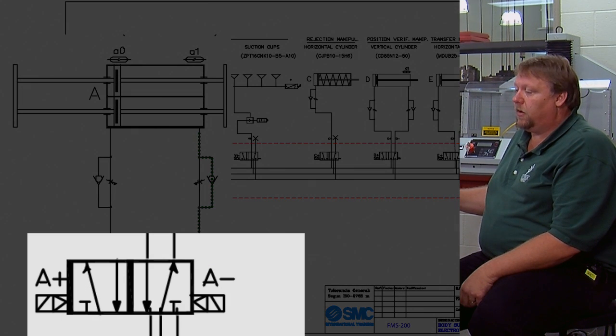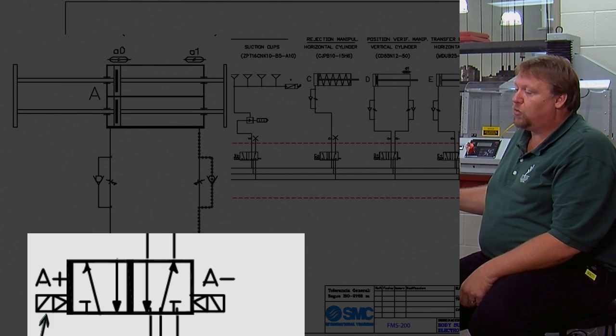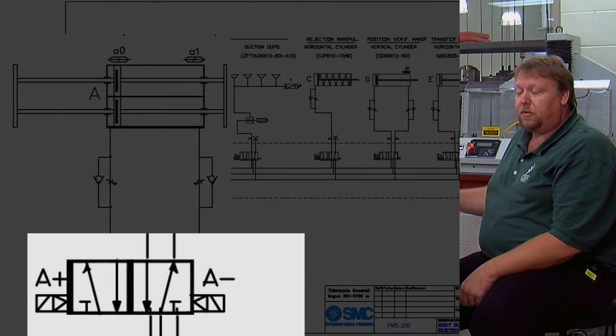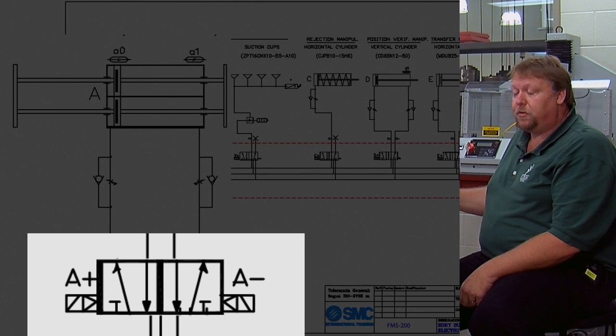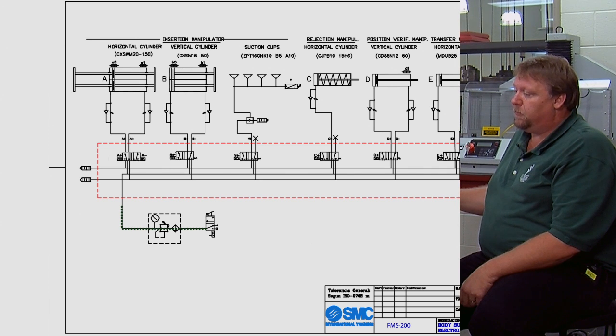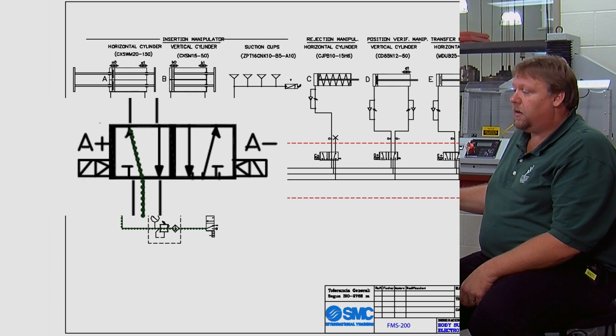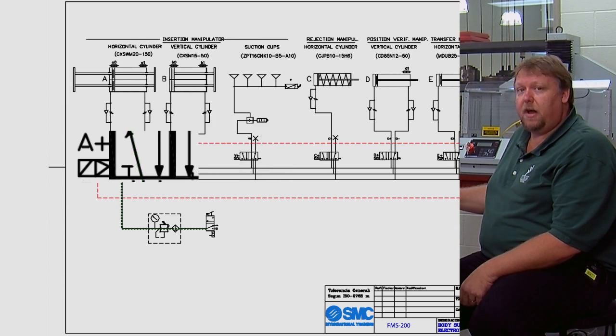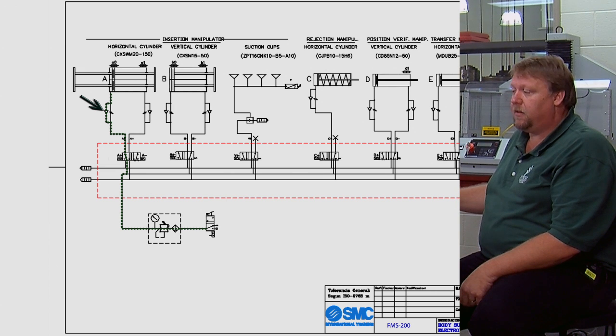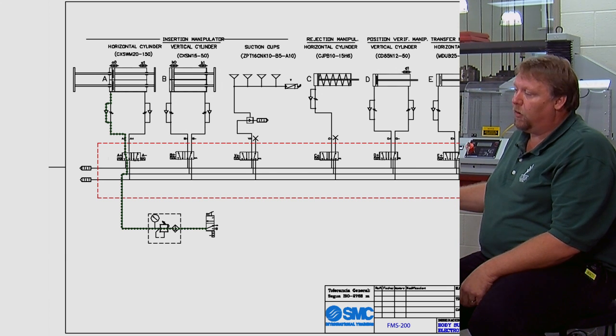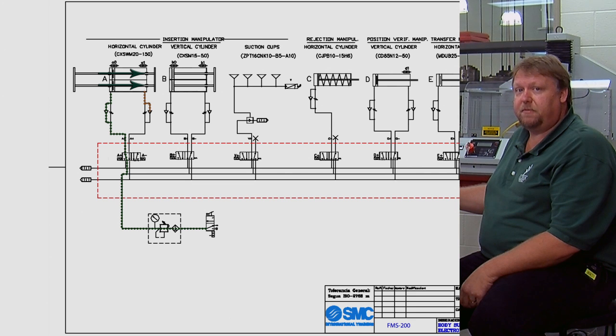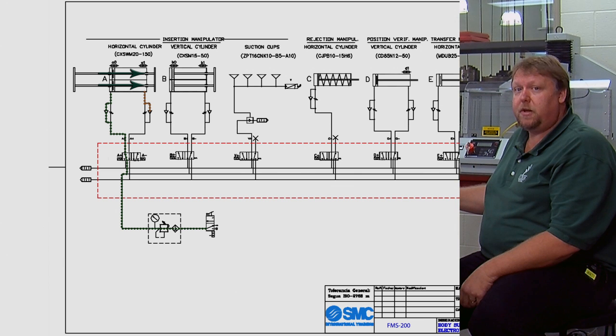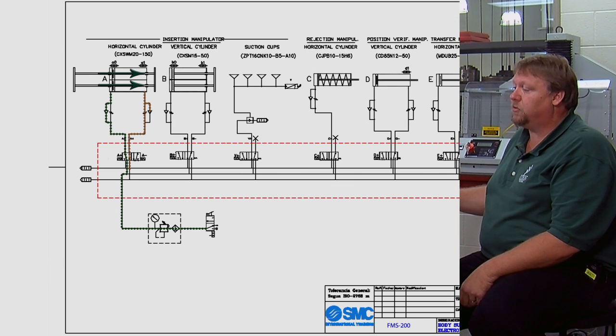Now if we look over here on the left side of this valve we can see the electrical coil with the square with the triangle through it. It says A plus on it. When we apply an electrical signal to this valve this envelope basically shifts over to the other side. So what we do then is we follow the air paths. So the air would then come through here, then it would go through this side, and then finally up through the metering device. Going through the flow control because it's a path of least resistance it's going to blow the ball off. With this cylinder already being extended now air is going to travel through here forcing it to retract. And as it retracts the air is going to come through here and hit this device right here which is our flow control. It's going to force that air through the metering device giving us speed control of the actual cylinder.